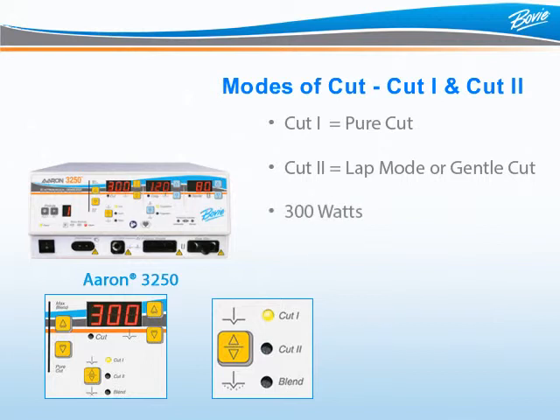Let's review the other two modes of Cut. The Cut 1 mode, or Pure Cut, means the unit is consistently delivering energy to cut through tissue, and like Cut 2, the Aaron 3250 offers up to 300 watts of power in Cut 1.